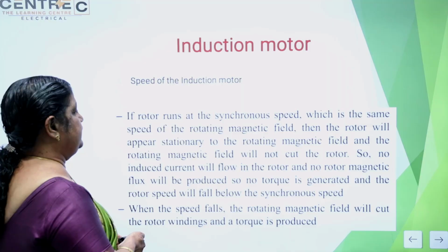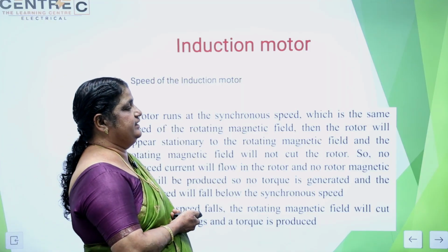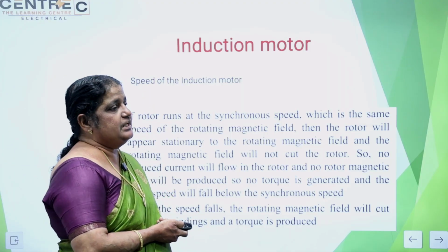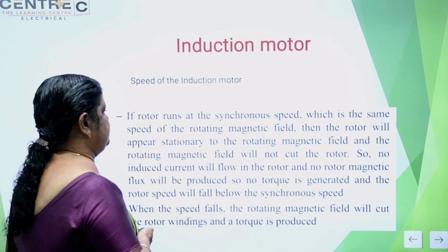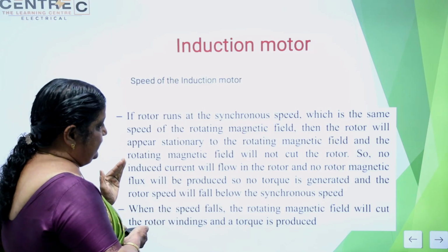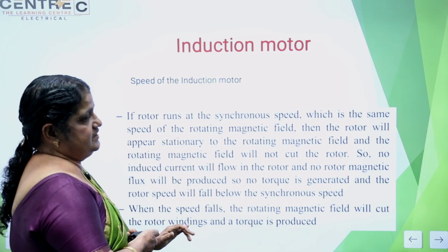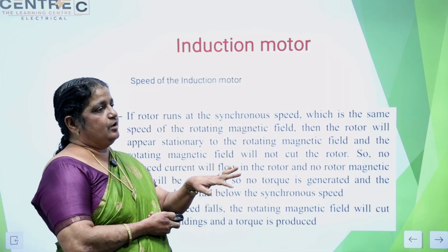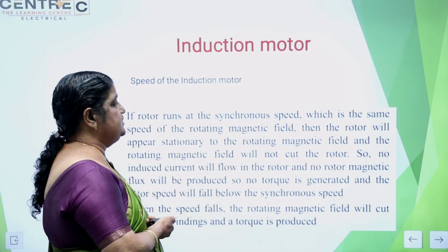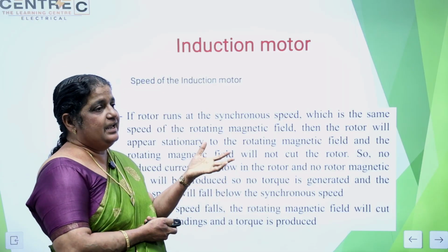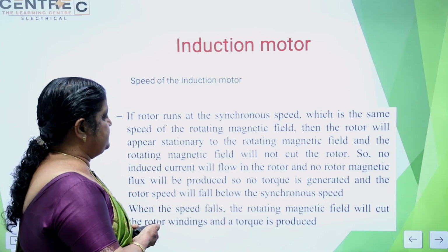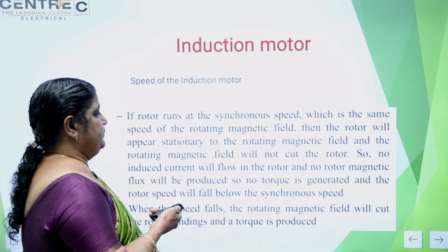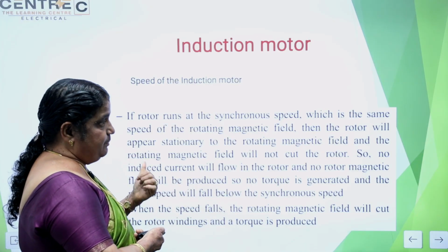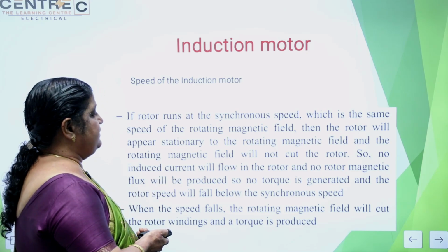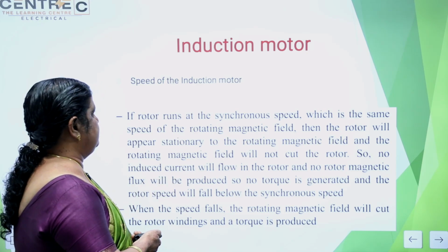Then the speed of an induction motor is not like that of a synchronous machine. In a synchronous machine, the speed is the same as the synchronous speed. But here, the rotating magnetic field speed is the synchronous speed. If the rotor rotated at the same speed, the relative speed would be 0, so the rotor would be stationary. So the speed difference is called slip, and slip is only relevant to the induction motor.